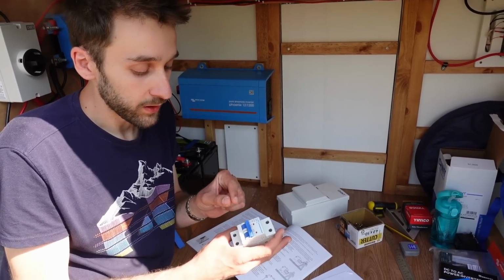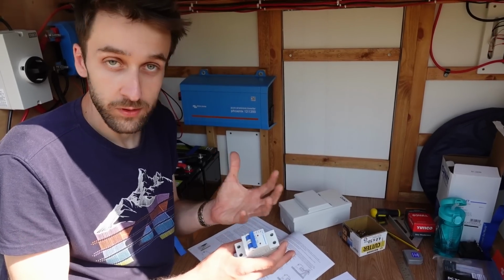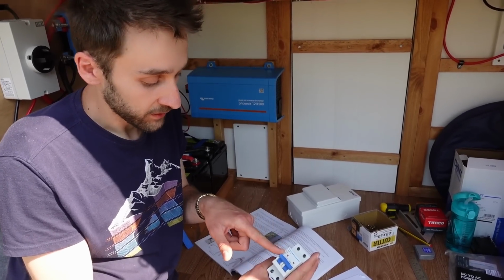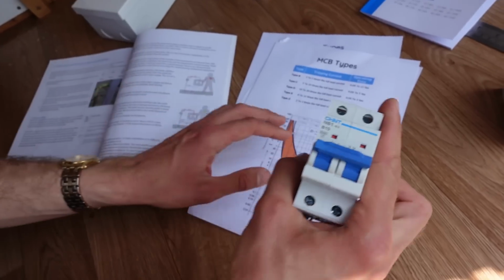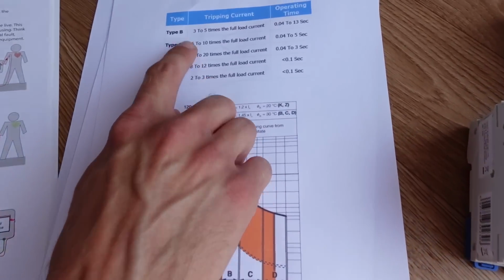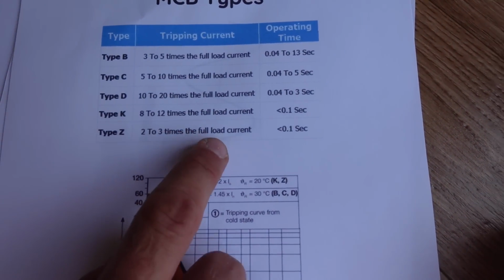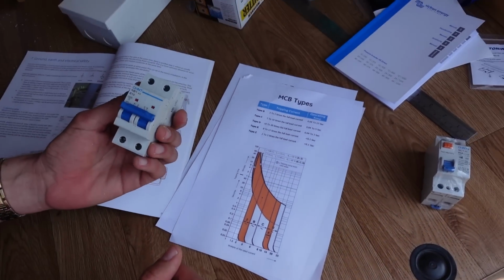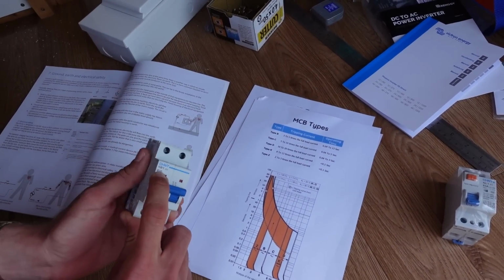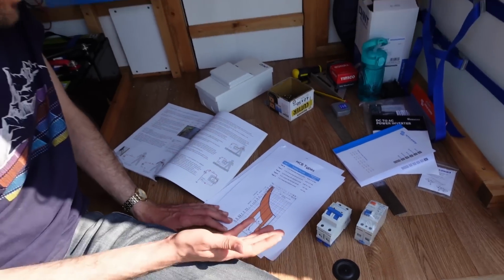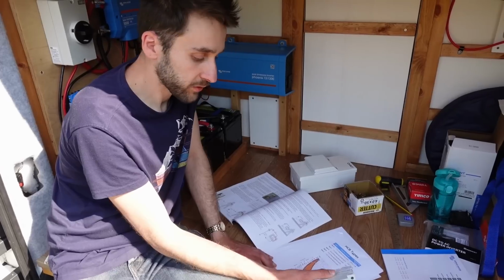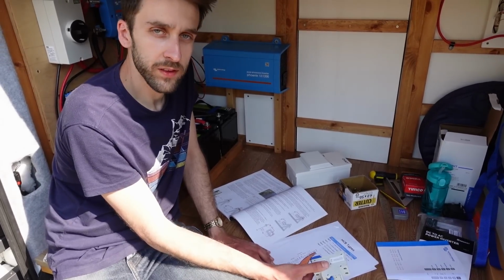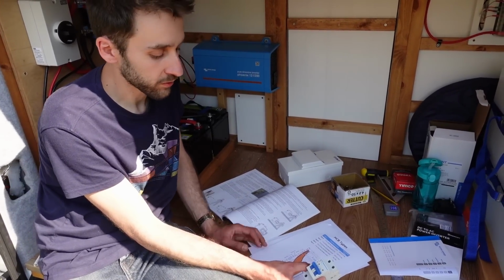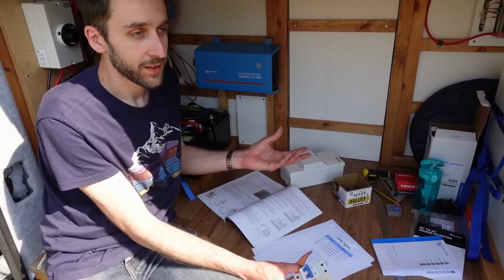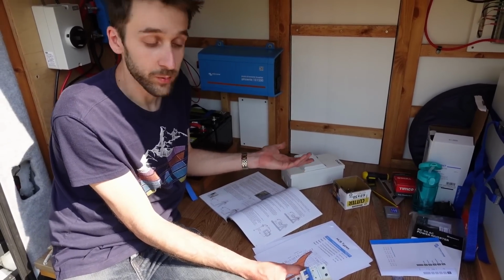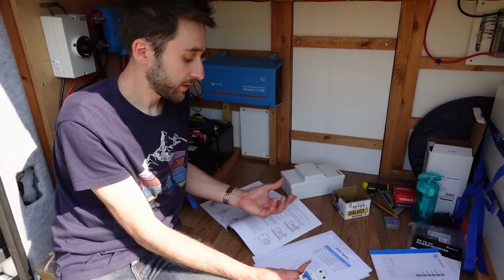And then there's a more instant part which is magnetic, and that trips really quickly, and there is a rating on here, a letter. So this one is B, and that corresponds to how quickly or how much current it takes for that second part to trip, which is something that's maybe a little bit counterintuitive, but yeah, this one won't actually trip until you put 30 to 50 amps through it. And then when it does get to that point, it's very fast on that part. The reason for that is actually by design. If you've got something that takes a lot of power to start up, you don't really want it to trip at exactly 10 amps, for example, because it'll just be tripping all the time and it'll be a nuisance. So it gives you a little bit of a buffer and then trips.